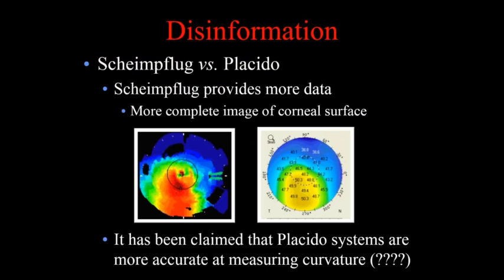A common statement from proponents of placido is that placido systems are inherently more accurate in producing curvature than elevation systems. That is somewhat of a disinformation. Scheimpflug clearly provides more data than placido does. Placido systems only image, under the best circumstances, about 8 millimeters, while Scheimpflugs can easily get out to 10 or 11 millimeters on the cornea. Placido systems rely on the tear film, so any tear film irregularity causes data loss. Scheimpflug is not a reflective system — it's an optical cross section, so surface regularity has no real effect.